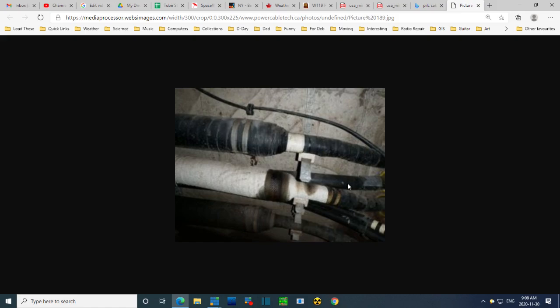Once they get the vacuum where they want it, they then allow oil into the tank. Thousands of gallons of oil go in. And then when they release pressure, the oil will flow into the tubules, or into the fibers of the paper, impregnating those tubes. That's why it's called paper insulated lead covered. They don't actually say the word impregnated, but it's impregnated paper.